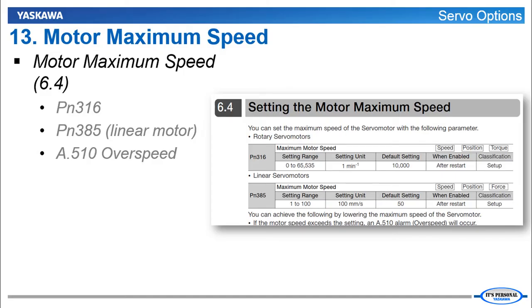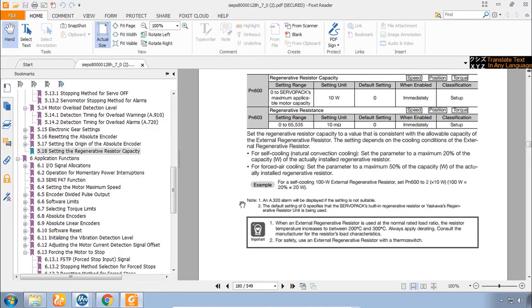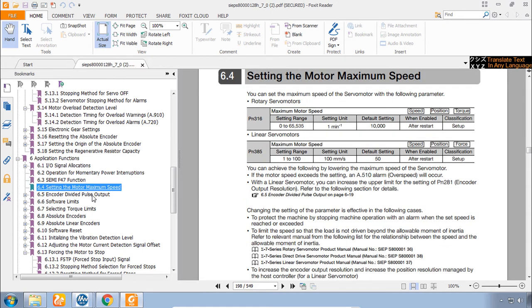Another new feature of Sigma 7 is the ability to limit the motor's speed. And this applies now to not just torque mode but also speed and position mode. with one parameter in RPM. Min minus 1 means RPM for rotary motors. And another parameter for linear motors in millimeters per second. It's a pretty straightforward parameter in section 6.4. If you exceed the speed in this parameter you get the alarm A.510 over speed alarm.